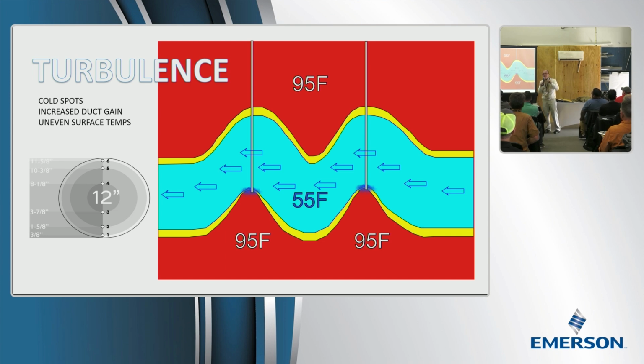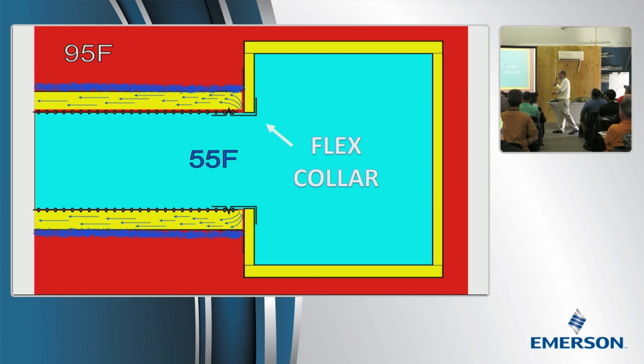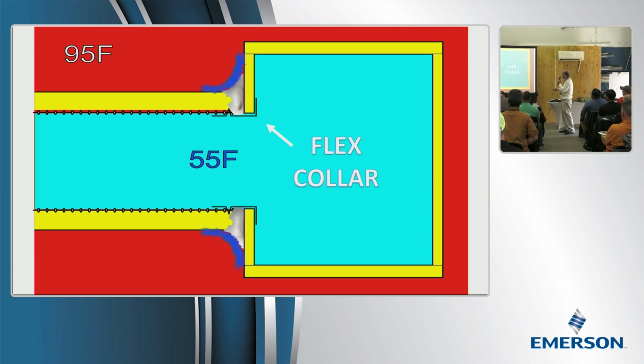And, you know, the internet is full of pictures of bad ductwork. We could make the class that. But you get it: run it straight, pull the kinks out of it, shorten it, hang it. These are the common sense things that will help. Flex collars, obviously, if they leak underneath the liner, then the liner will get cold. But the other way that's a problem is if you create thermal bridging. A metal collar is colder than the flex duct, and the metal collar is on the inside. See, the air barrier is switching from the outside to the inside. So on the trunk line, the air barrier is on the outside, but on the flex duct, it's on the inside. The tap collar is where it goes from the outside to the inside.